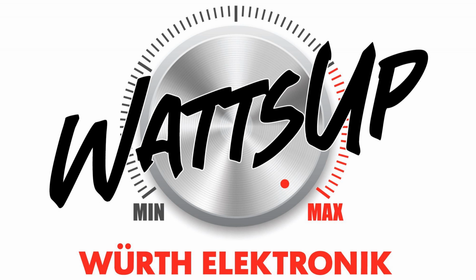In regular operation, when you have these two Y caps and the X capacitor, you have to take care about the leakage of these capacitors, because according to the norm, you have to make sure that the current on the PE doesn't trigger your fuse. You sometimes have a safety fuse, and you cannot put too big values here.